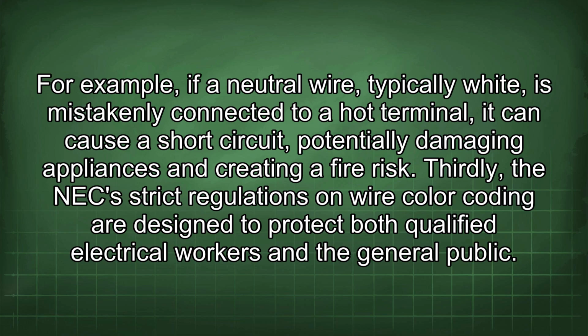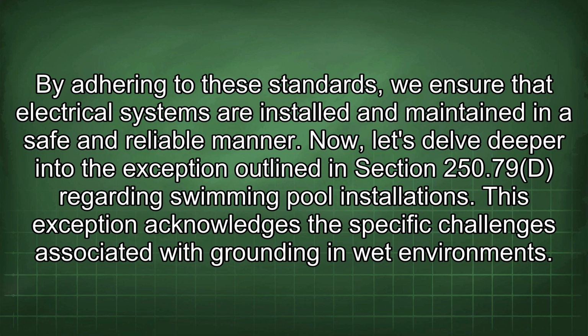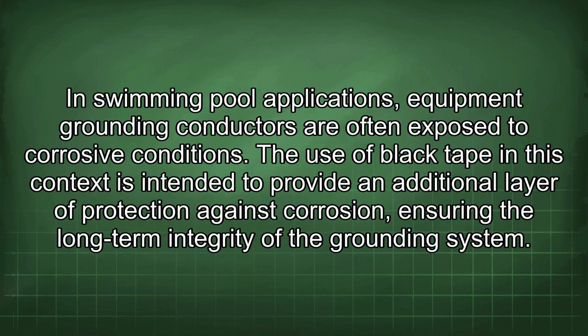Thirdly, the NEC's strict regulations on wire color coding are designed to protect both qualified electrical workers and the general public. By adhering to these standards, we ensure that electrical systems are installed and maintained in a safe and reliable manner. Now, let's delve deeper into the exception outlined in Section 250.79(D) regarding swimming pool installations. This exception acknowledges the specific challenges associated with grounding in wet environments. In swimming pool applications, equipment grounding conductors are often exposed to corrosive conditions. The use of black tape in this context is intended to provide an additional layer of protection against corrosion, ensuring the long-term integrity of the grounding system.